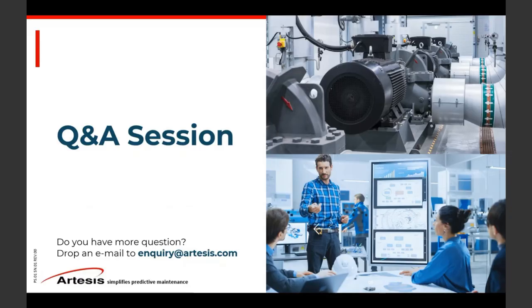So does it report bearing lubrication faults? Yeah, if it sees and understands the context of a potential bearing issue, it could be due to misalignment or lack of lubrication. Probably it would list those two as potential root causes, not necessarily lubrication. Sometimes it does that, but of course, it will improve that analysis over time, especially if you're repeating the analysis on the same equipment.